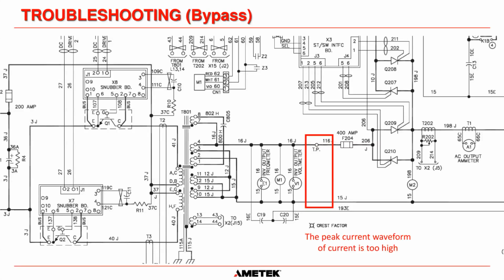And the last alarm that I think I'm going to discuss from the Micro-ferro system is the crest factor board. It's very difficult to monitor an AC waveform, and if there is any peak currents being seen by the load circuits out here. So we do have a crest factor detection circuit that is looking specifically for peaky load current, because peaky load current, you know, you could measure this with an amp clamp.